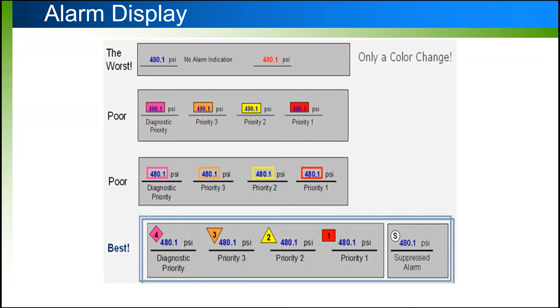Let's look at this in a bit more detail. We use a square for priority 1, and you put an outline around each of the shapes because it makes it more readable. So you put a shape around it, a specific color, and a number, and use that every time you display your alarms. You also display when an alarm is suppressed or shelved.